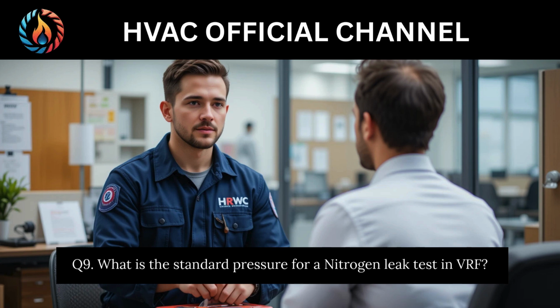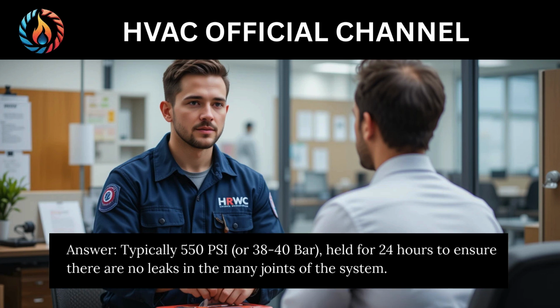Q9. What is the standard pressure for a nitrogen leak test in VRF? Answer. Typically 550 psi, or 38 to 40 bar, held for 24 hours to ensure there are no leaks in the many joints of the system.